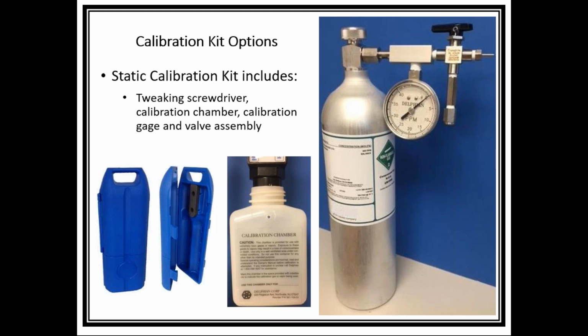The way this is done is quite simple. We allow you to inject a very high concentration of a gas in a very small volume. So we take advantage that we have a cylinder filled with, let's use hydrogen sulfide as an example, a cylinder of gas of 1,000 ppm, and when that valve on the top of the cylinder is open, we allow the gas to flow into a very specific volume, a 1.2 cc volume. Using the pressure gauge, we've converted pressure over actual parts per million, so that when you open this valve up, you can then fill it to a specific 15, 20, 25 ppm.